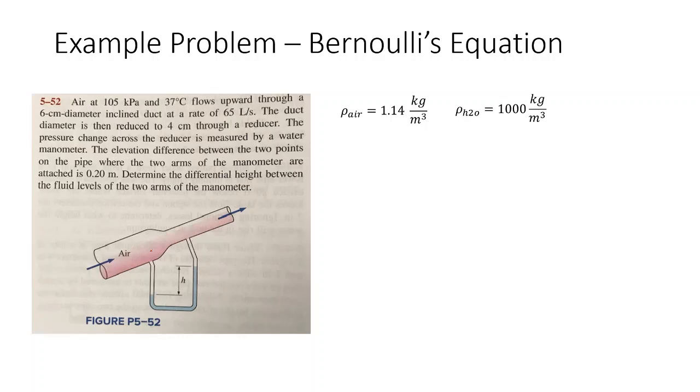Our next step is to use this volumetric flow rate to find the velocity of our fluid through each duct segment. So Q of air is 65 liters per second. We're going to want to convert this into meters. If we recall that there's a thousand liters per cubic meter, we can convert this to 0.065 cubic meters per second.